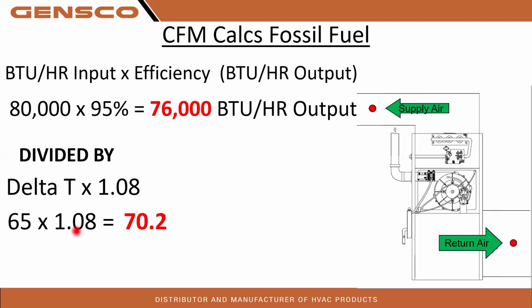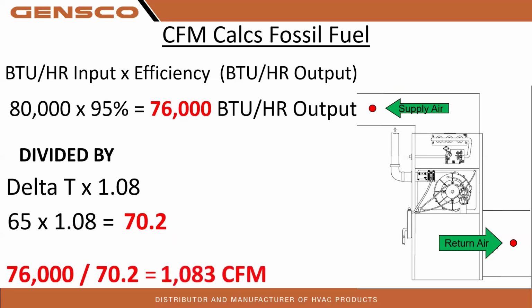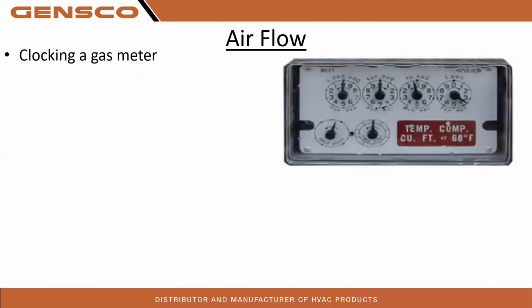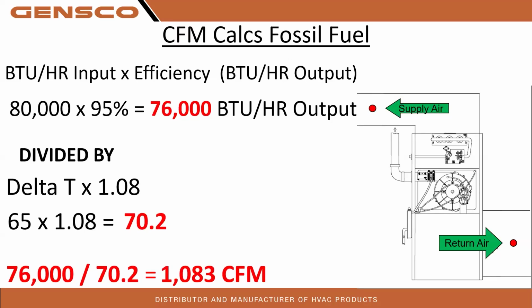So 65 times 1.08 is 70.2. 76,000 divided by 70.2 is 1,083 CFM. So this is a great way to actually see what your units are pushing. But with technology nowadays, we just cycle through our digital app or the circuit boards, and we can actually see what the CFM is. With online diagnostics on our Link communicating or our old 1050 communicating systems, if it's a communicating indoor, we could see that static pressure, we could see that target airflow CFM, we could see everything it's doing.